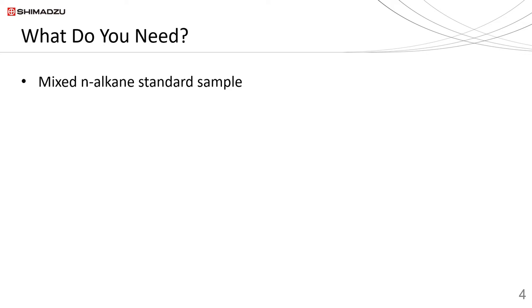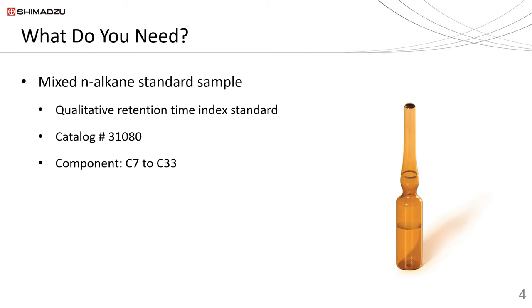To perform AART, a mixed n-alkane standard solution is used as retention index standards to predict retention times of target compounds. The n-alkane standard needs to be prepared with an appropriate range of carbon numbers depending on target compounds, and at a concentration that can produce differentiated peaks in the total ion chromatogram. You may use the readily available n-alkane standard from Restek Corporation called the Qualitative Retention Time Index Standard.